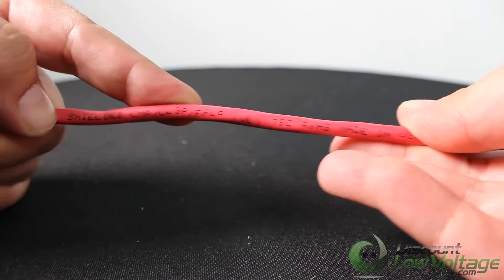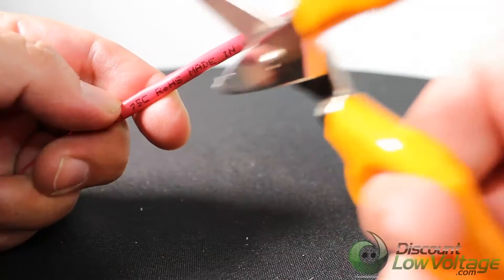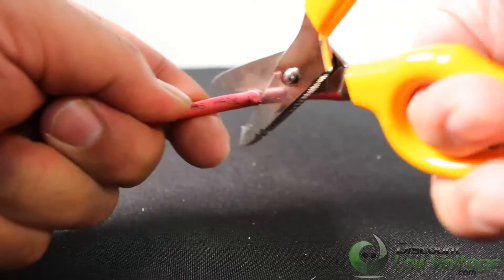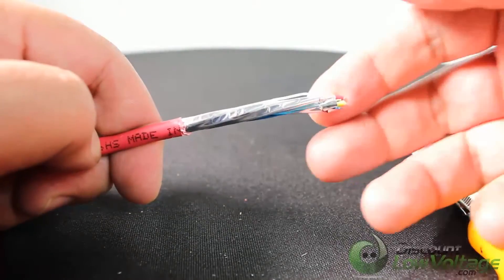All plenum listed fire alarm cables provide compliance to NEC article 760, NEC article 725, FPLP, and CL3P. These are rated for power limited 300 volts.